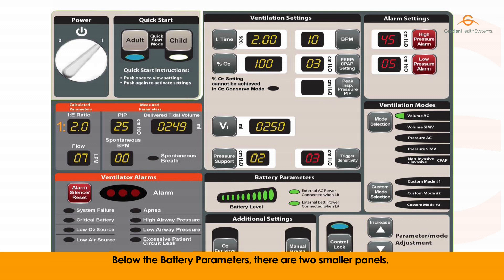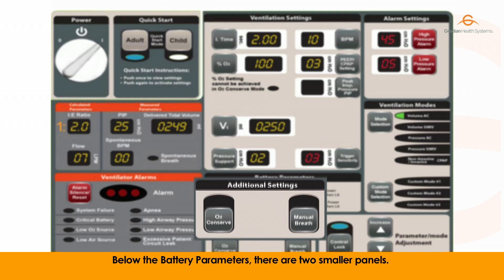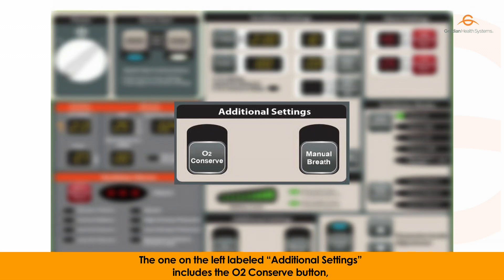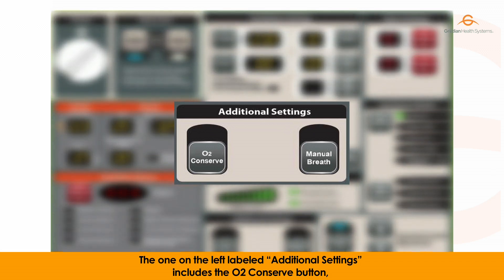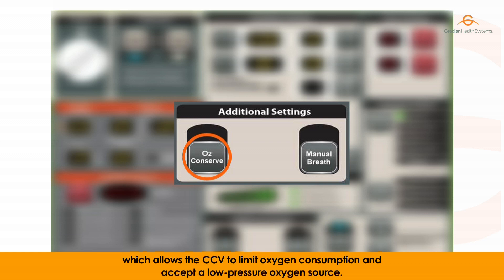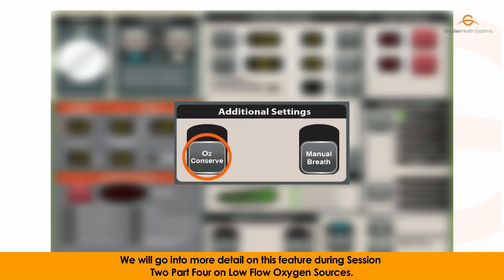Below the battery parameters, there are two smaller panels. The one on the left labeled additional settings includes the oxygen conserve button, which allows the CCV to limit oxygen consumption and accept a low pressure oxygen source. We will go into more details on this feature during session 2, part 4 on low flow oxygen sources.